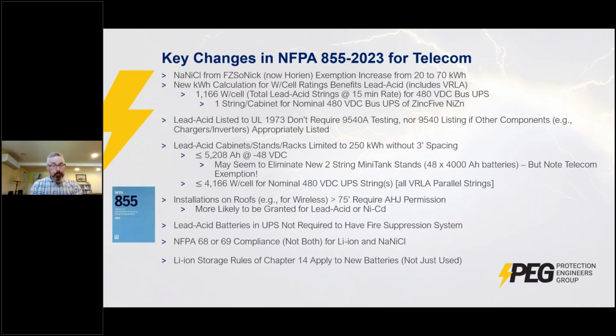And regarding NFPA 68 and 69, those are NFPA standards to address explosion control. That's NFPA 68, like relief panels, sort of controlling the explosion and how much damage it does. NFPA 69 is explosion prevention, venting gases or taking other means to prevent an explosion. The current 2023 edition of 855 allows you to do either explosion control or explosion prevention for lithium-ion or sodium nickel chloride, but you don't have to do both. You've got to pick one or the other.